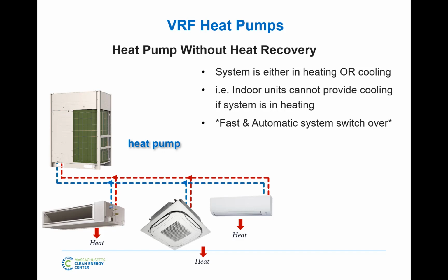So if it was in heating in the morning, like this morning, right? We woke up, it was high 40s, low 50s. It's in heating mode because all the set points are at 72. The rooms are a little cold. It's all in heating mode. When the sun comes around, like it will this afternoon, and it starts to get warm, it's going to see all the room temperatures go up. So it's going to say, okay, now on average, I need cooling. It'll switch in 5, 10 minutes. It'll do automatic switching, and it'll start going into cooling mode.